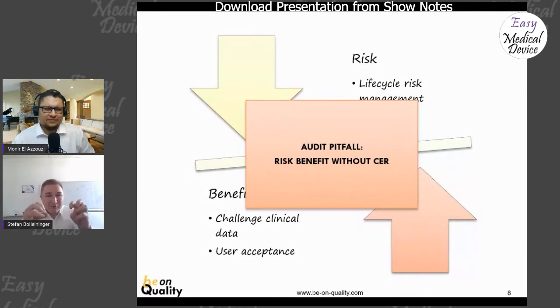So grab your usage data from other devices, like a MAUDE database for example, or any kind of recall databases, or any kind of complaint data. Take that also into your risk benefit, that's part of it. Then once you get through that, you can have a good calculation of the risk benefit on the risk management side. So the risk management report gives you a finalized value, that's it.